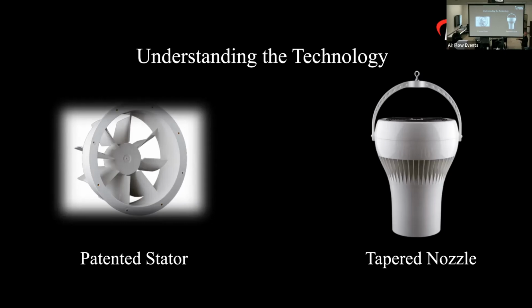Say, for instance, we've got an Air Pear Model 25. Each fan covers 1,200 square feet of destratification. Based on that, and then an 18 to 28 foot ceiling, based on those two figures right there, then you can start designing a series of fans that's going to go in for that space. At least it gives you a good starting point. And the stator, again, within the fan helps control that airflow so that the air column goes down, hits the floor, comes back up, and then continues to recirculate.